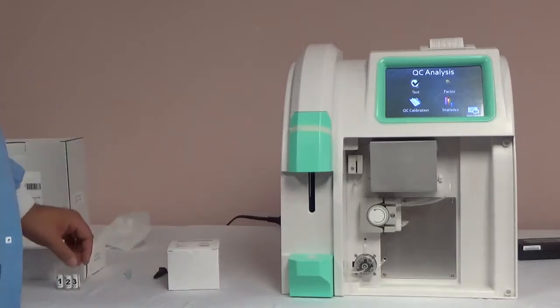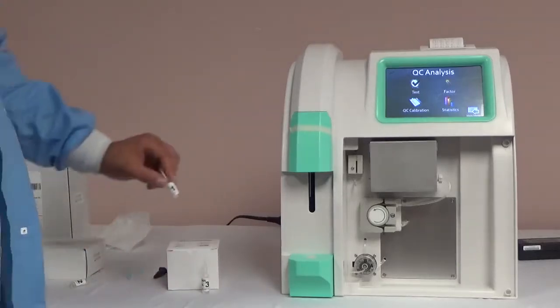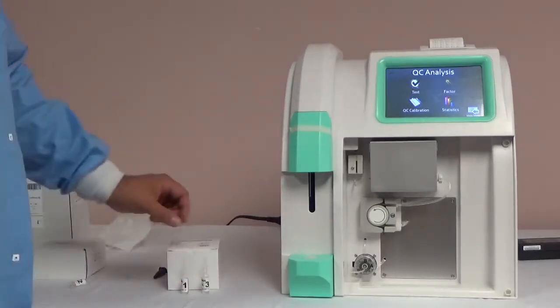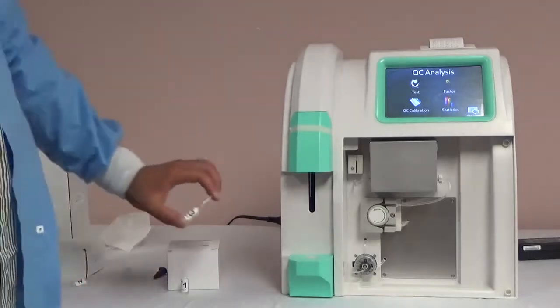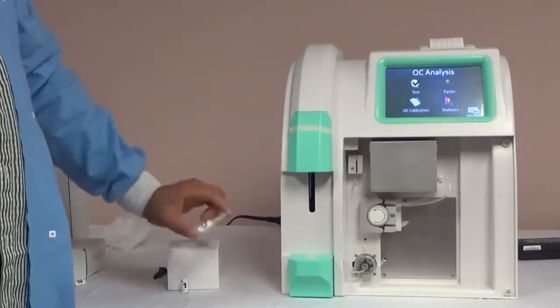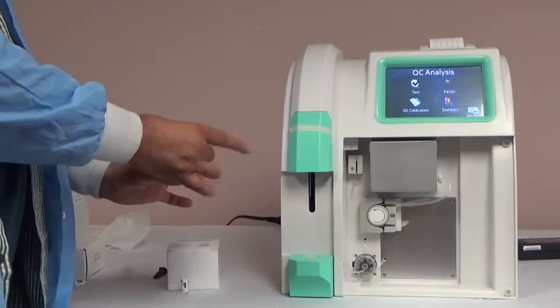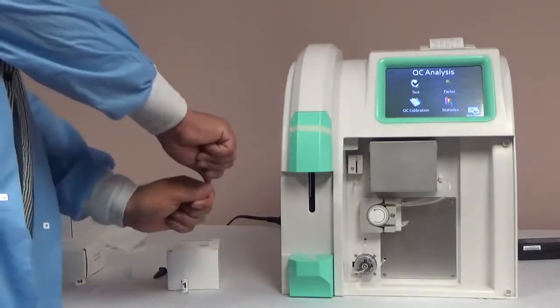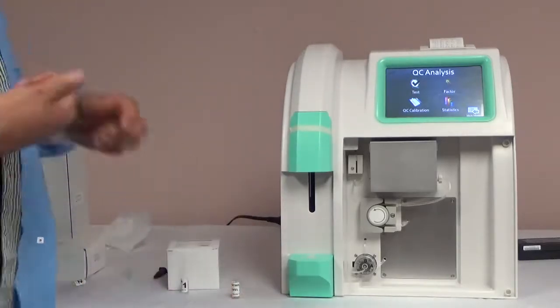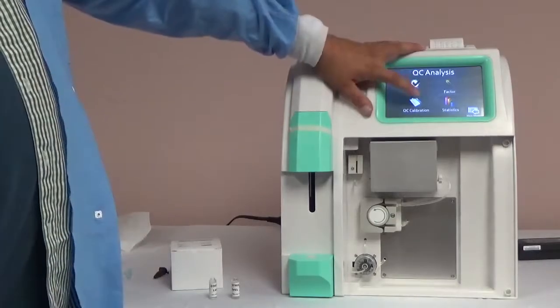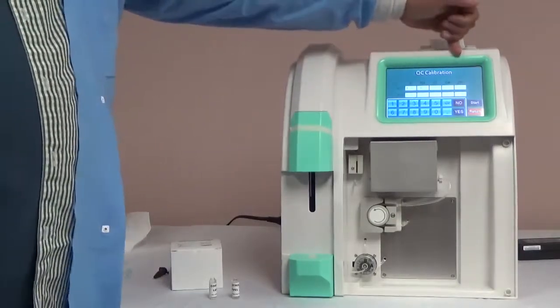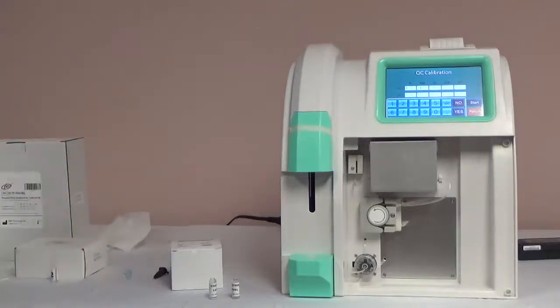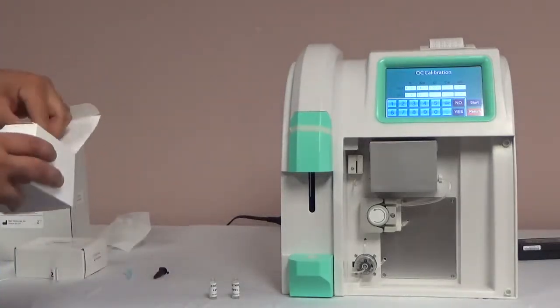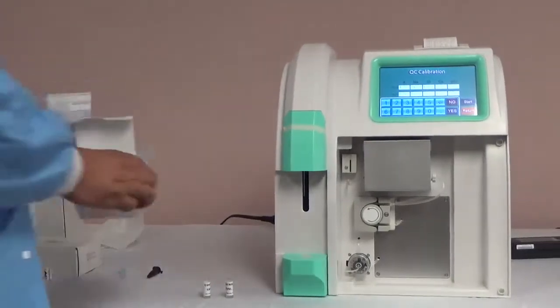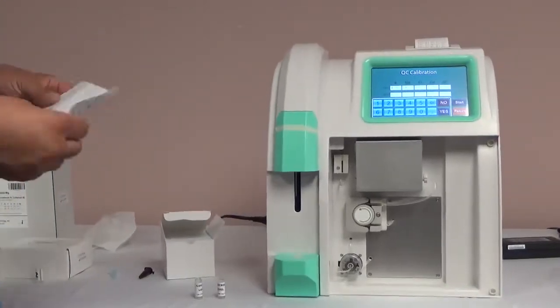To do QC calibration, you will need linearity control material. The linearity control material includes levels 1, 2, and 3, but you will only need levels 1 and 3 for the QC calibration. To prep the solutions, shake the bottle, flick the top, and snap the top off. You will set the targets for QC calibration, which can be found on the insert sheet of the product. For each level of QC, find the analyzer and the level that you will be testing, enter the target and the range, hit start, and begin the calibration.